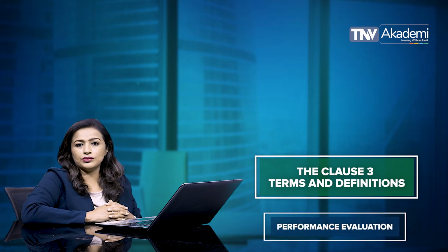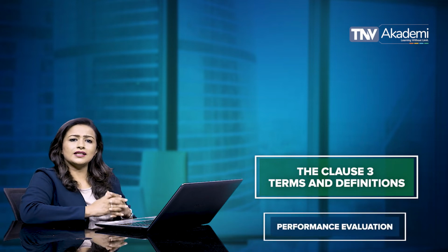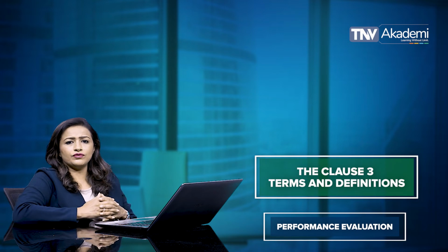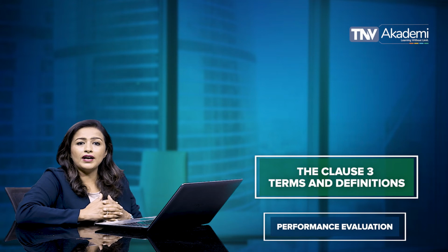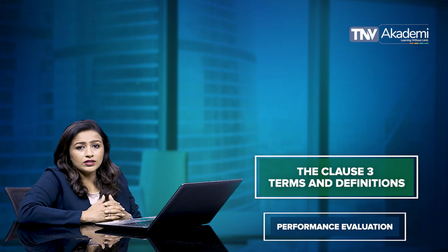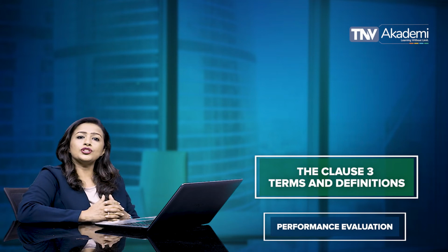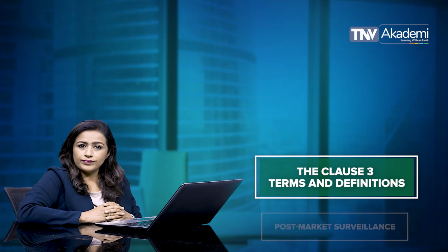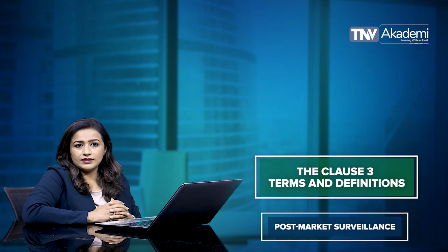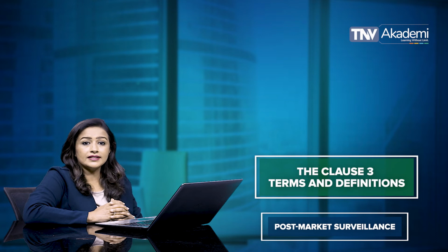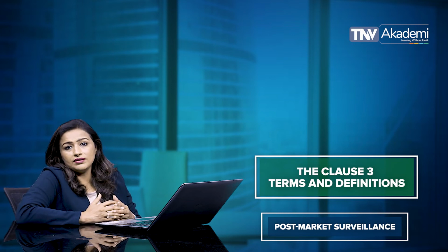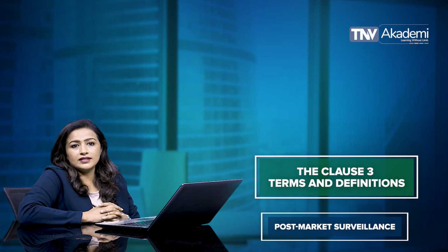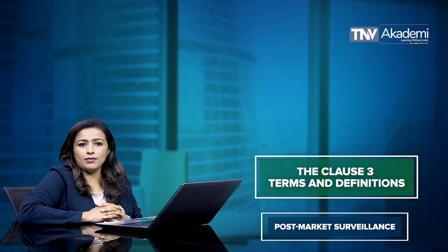Performance evaluation. Performance evaluation is assessment and analysis of data to establish or verify the ability of an in vitro diagnostic medical device to achieve its intended use. Post-market surveillance. Post-market surveillance is a systematic process to collect and analyze experience gained from medical devices that have been placed on the market.